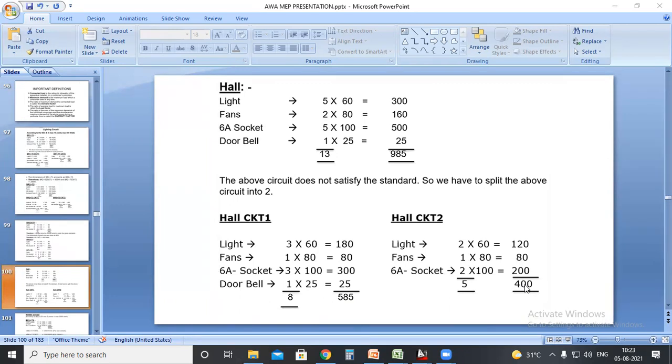So this is how we prepare the lighting circuit as per the standards. This is as per the Indian standard, and we are sticking very strictly to the 10 points and 800 watts. If 1 or 2 points are just increasing, it is not an issue, because as I mentioned, the total ampere is the main part. If the ampere crosses a particular limit, it will not act as a light circuit. So if you provide a 6 ampere breaker on 1.5 sq mm wire, in future it may cause an overcurrent issue and the wire may get burned.